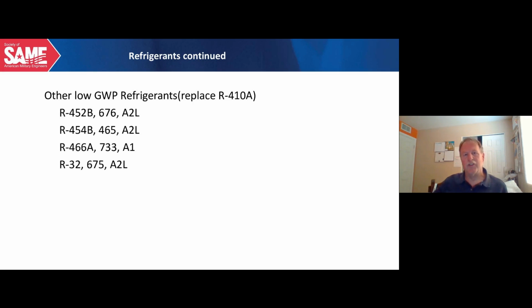Now, these refrigerants are all high pressure refrigerants. They are replacements for 410A. None of these are currently available in the United States because they haven't been adopted into the code. The next code revision that we will see is the 2024 series of the International Code Council code. So the International Mechanical Code doesn't have all the items in it related to safety for these refrigerants. But we've got R452B, R454B, and R32 all have global warming potentials in the 400 to 600 range.